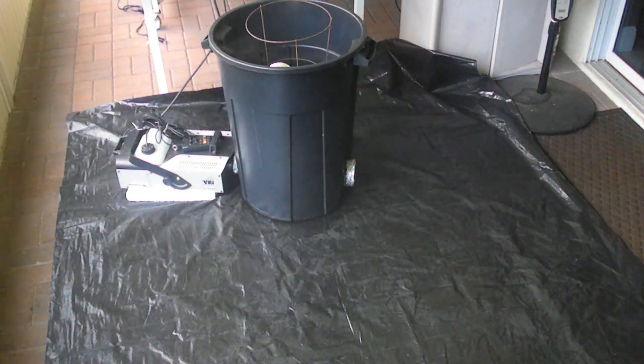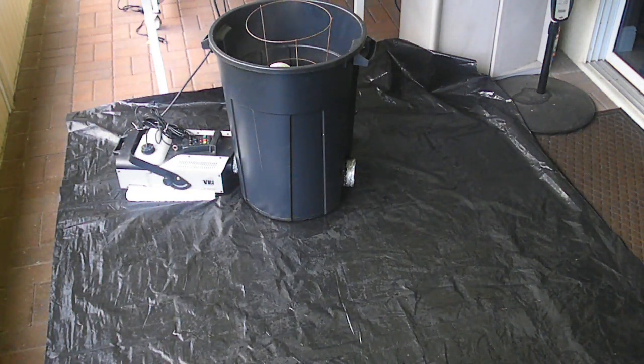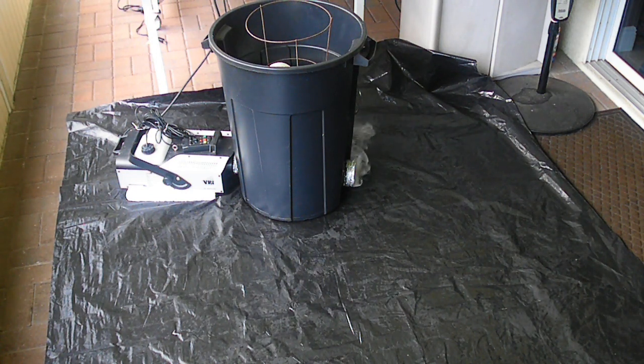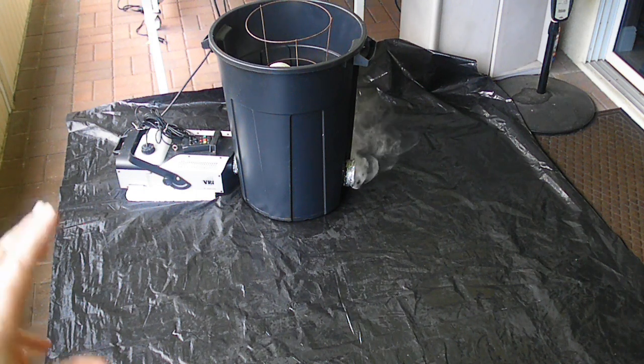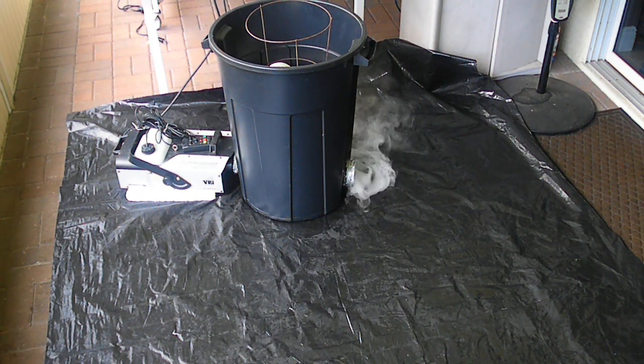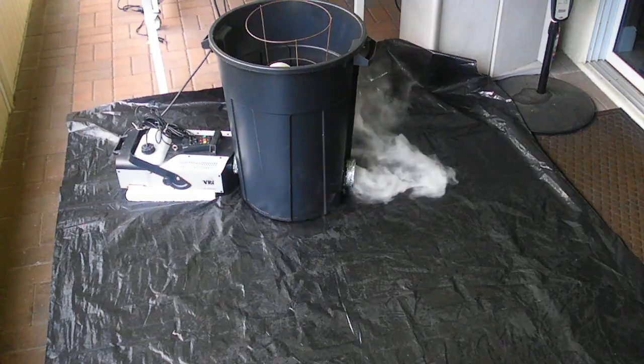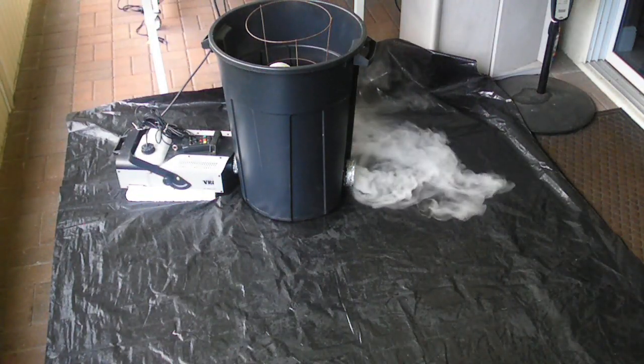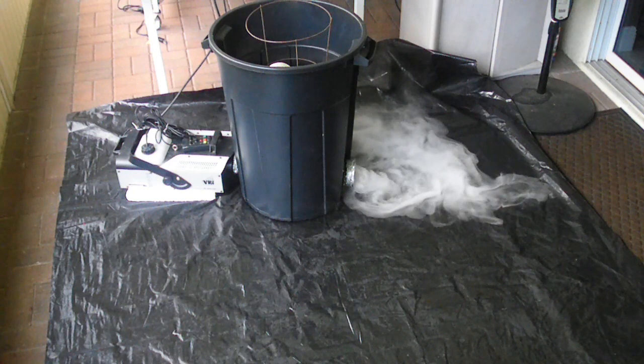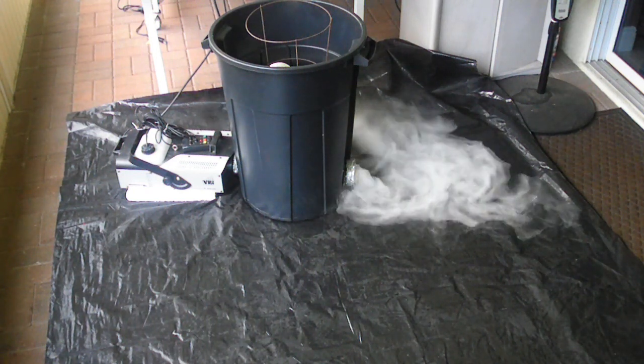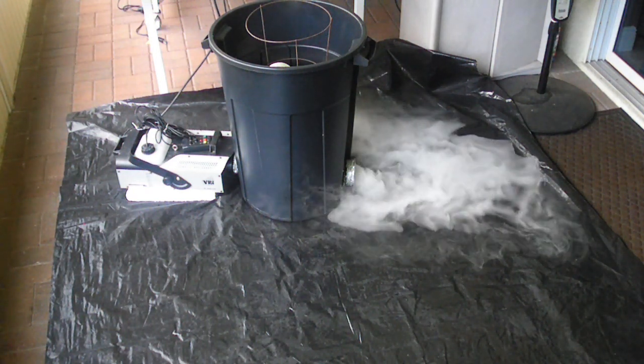By the way, some people say, as another tip, to blow air in there, back it up so you can throw air into your chiller with the fog. Well, that does cool it down a little bit initially if you're not getting it cold enough. But what you're also doing is just taking outside air, drawing it in there, and using your ice up trying to make that outside air cool.